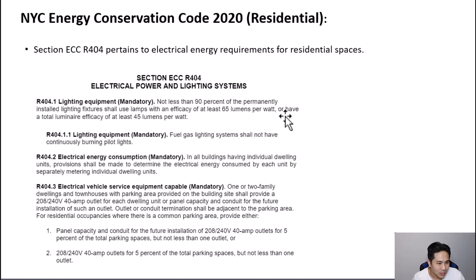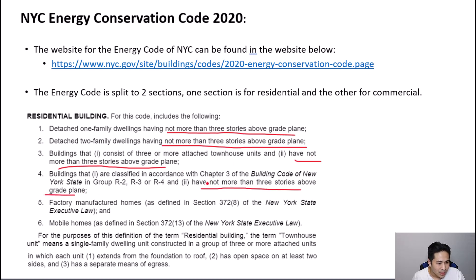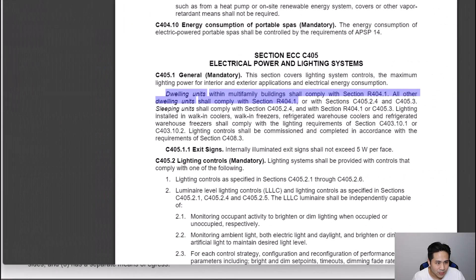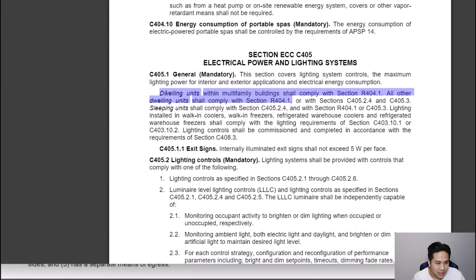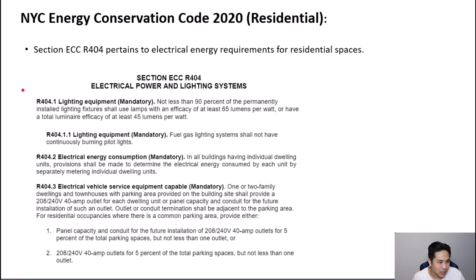The residential section R404.1 simply requires that lighting meets the efficacy requirements. The residential definition requires buildings to be not more than three stories above grade. However, the commercial section states that dwelling units can comply with R404.1 regardless of the number of floors. In summary, all dwelling units can follow section R404.1.